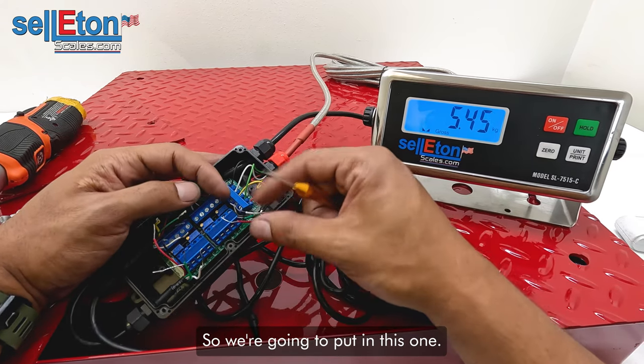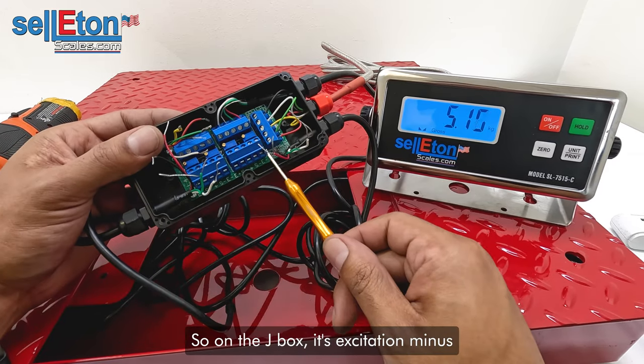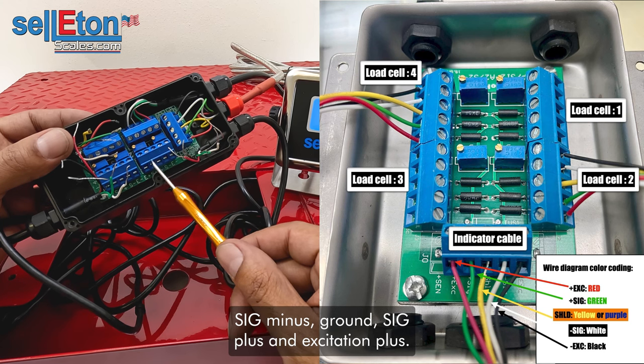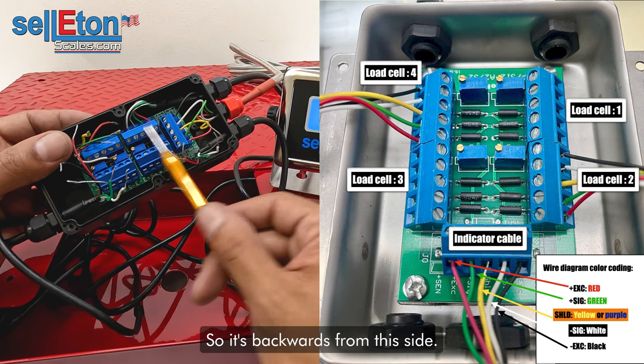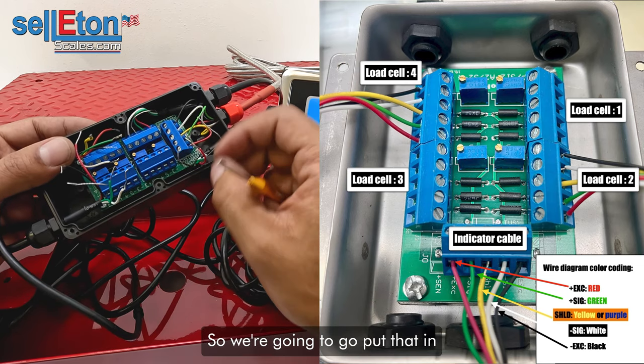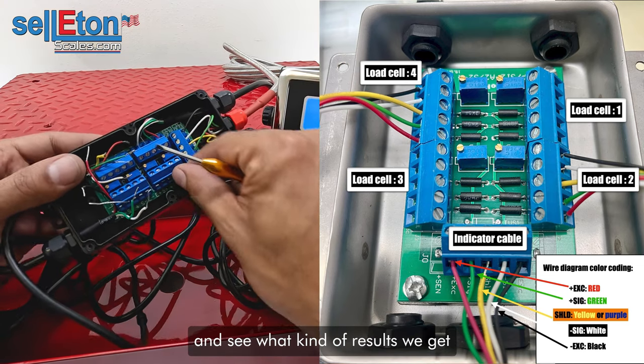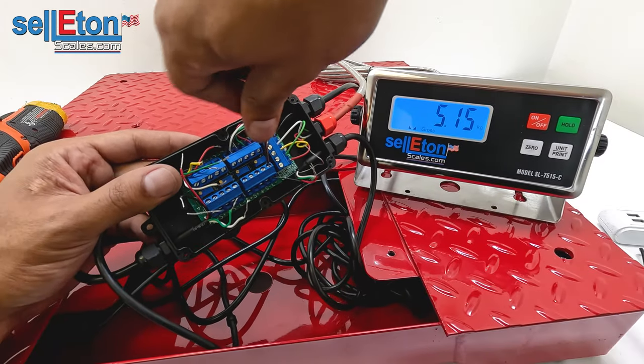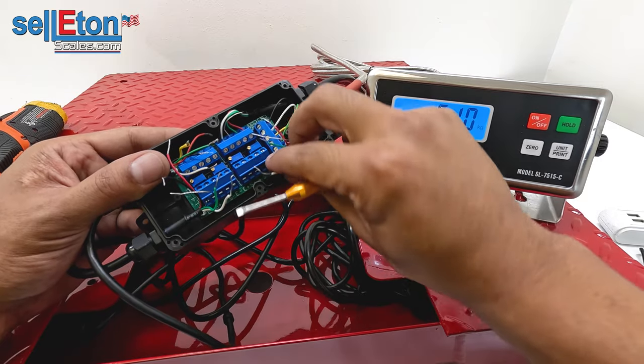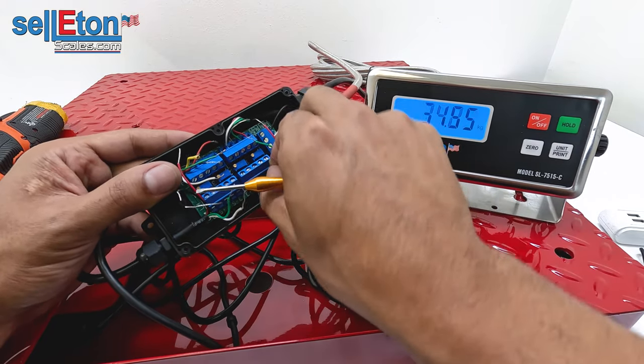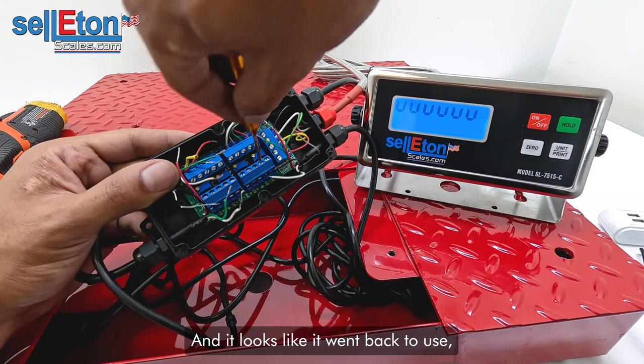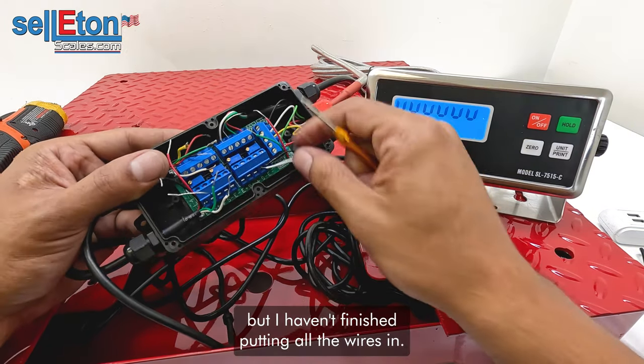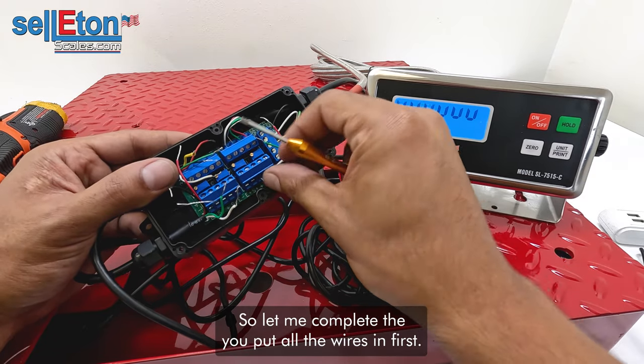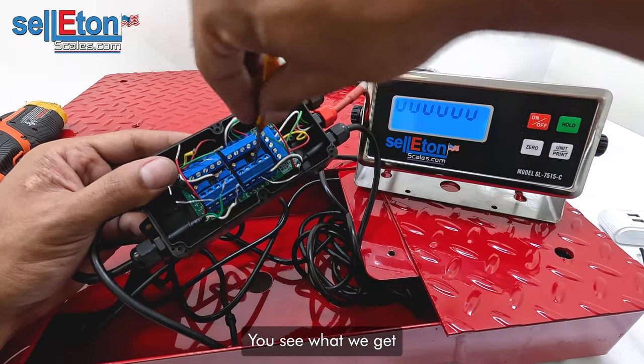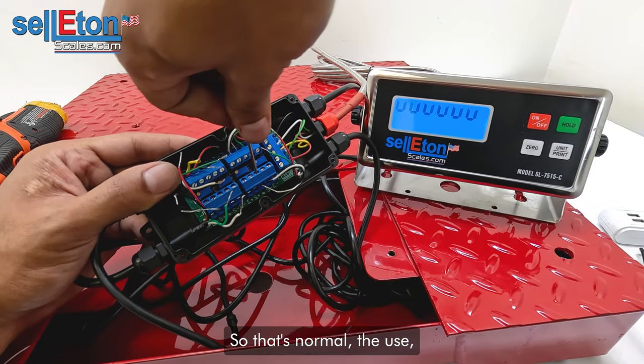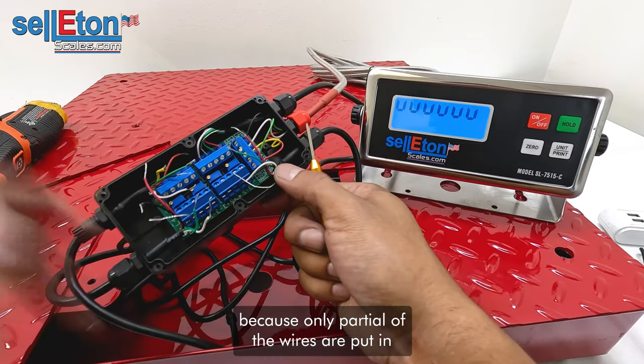So we're gonna put in this one. On the J box, it's excitation minus, sig minus, ground, sig plus, and excitation plus. So it's backwards from this side. So we're gonna put that in and see what kind of results we get. Okay, it looks like it went back to use, but I haven't finished putting all the wires in, so let me completely put all the wires in first, and we'll see what we get. So that's normal, the use, because only partial of the wires are put in.